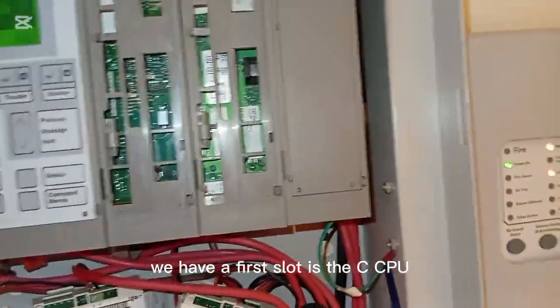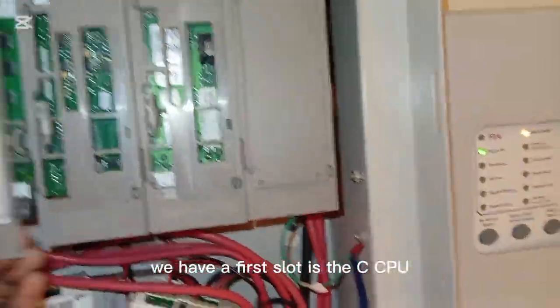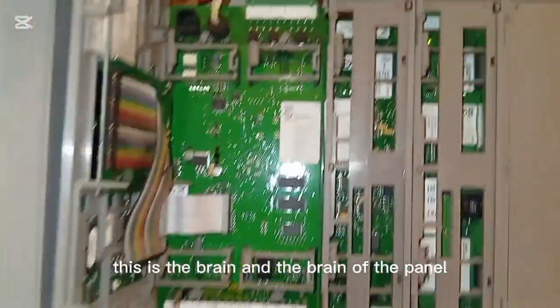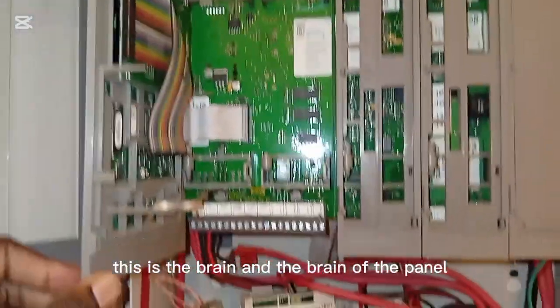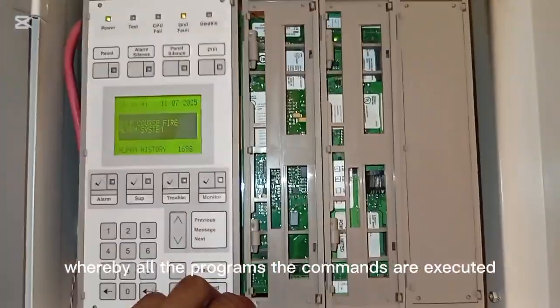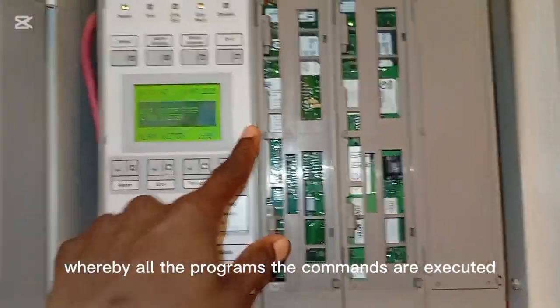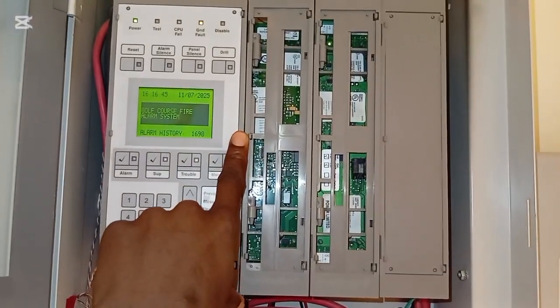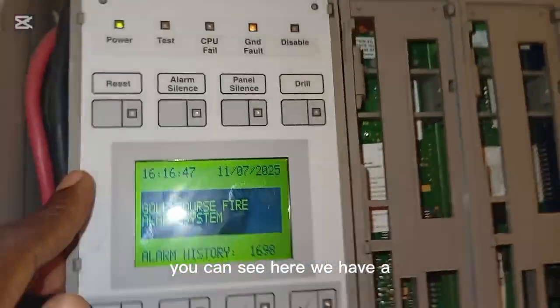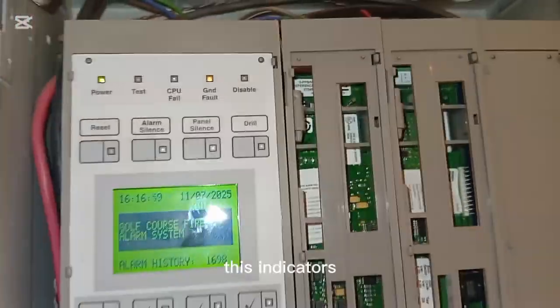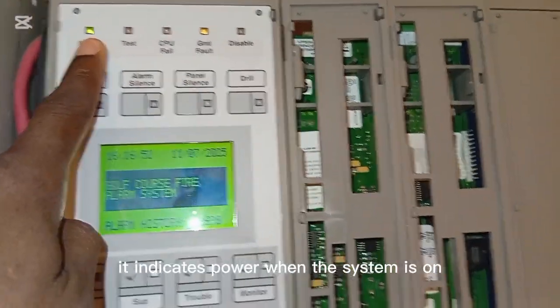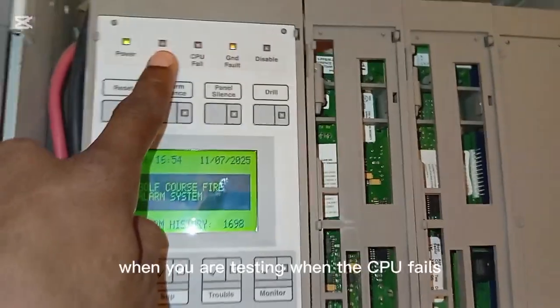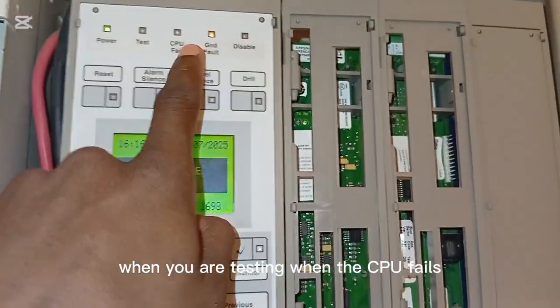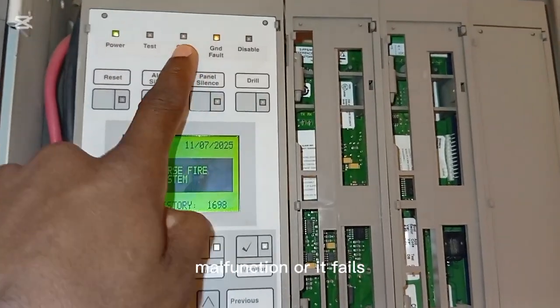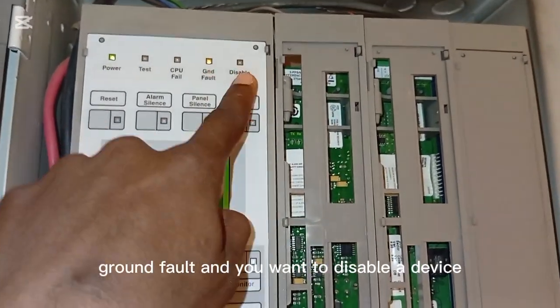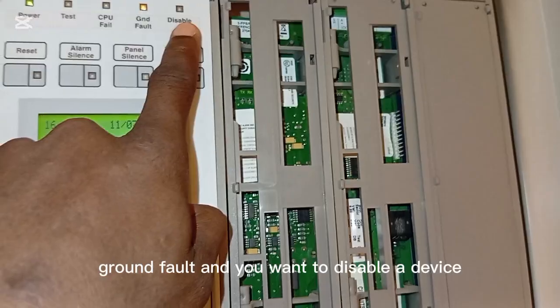We have the first slot, which is the CPU. This is the brain of the panel, whereby all the programs and commands are executed. You can see here we have these indicators. They indicate power when the system is on, when you are testing, when the CPU fails or malfunctions, ground fault, and when you disable a device.